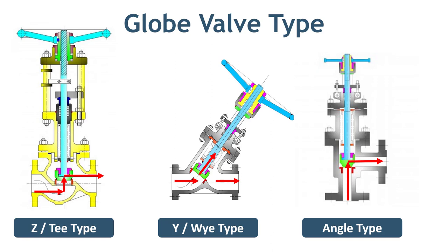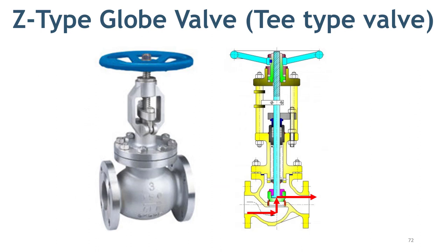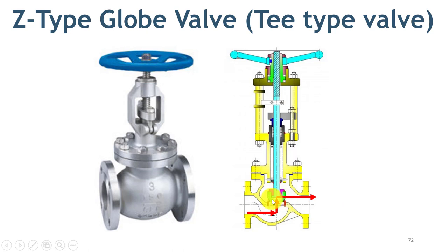On this slide, you can see the three most common types of globe valve used in piping. The first one is Z-type or T-type. This is the one that has a globular body. It is called Z-type because the fluid flows in a Z shape through the valve. The same valve is also called T-type because the disc and seat make a T shape. This type of globe valve is used where pressure drop is not a concern and a high degree of throttling is required.